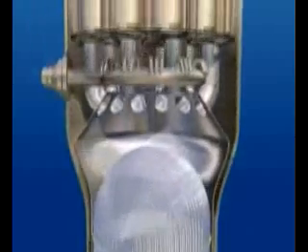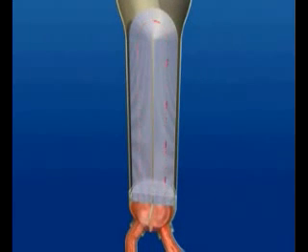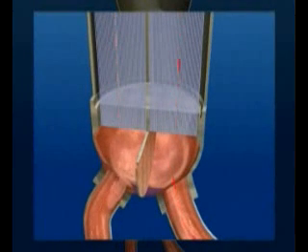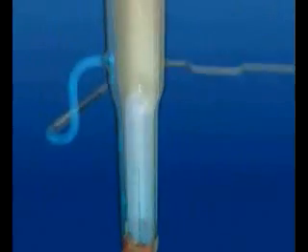Within the steam generator, heat stored in the primary circuit water is transferred to a secondary circuit. The heat exchange occurs within a bundle of around 6,000 inverted U-shaped tubes. The heated water enters the bottom of the steam generator, transfers its heat to the secondary system water through the U-tubes, then returns to the reactor vessel for a new cycle.